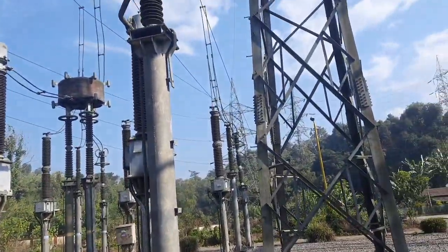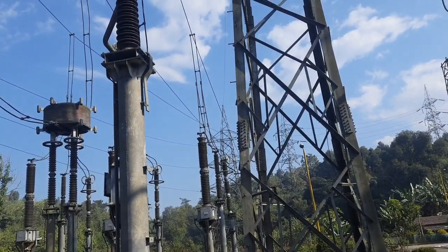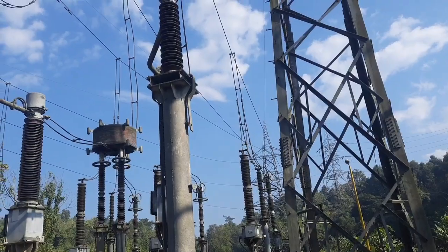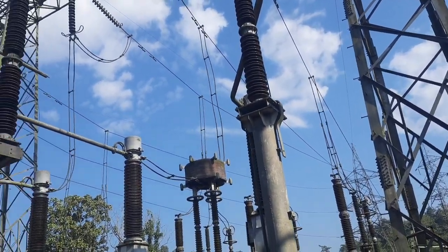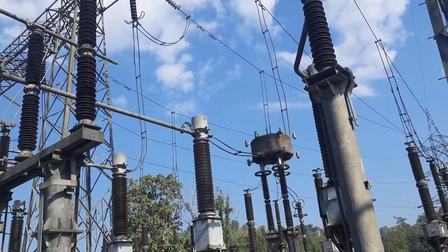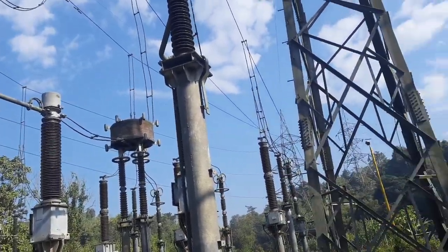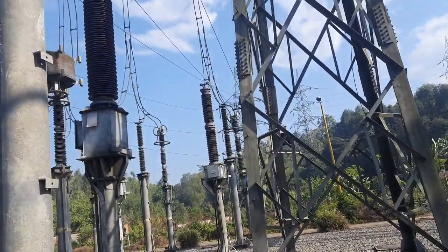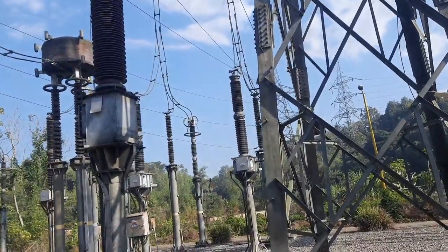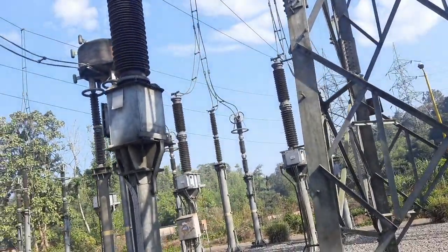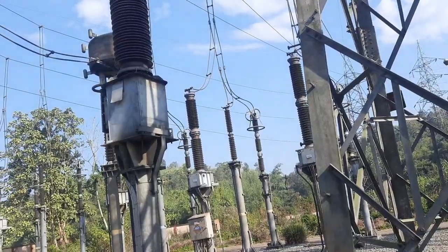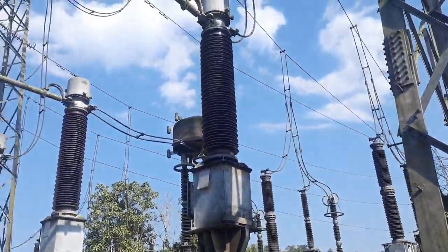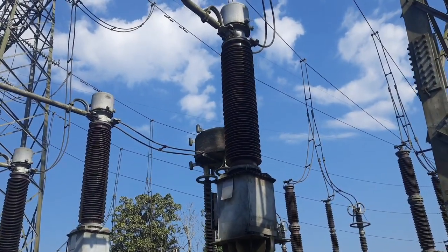So what I've just shown you is the general arrangement of the surge arresters, your capacitive voltage transformers, then your Wavetrap, and then your CTs. It has to be arranged like this. First is always the surge arresters. Just like I said, it's like the Border Security Force. It comes first, and then your CVT is like your check gates, which are actually manned by the local police.